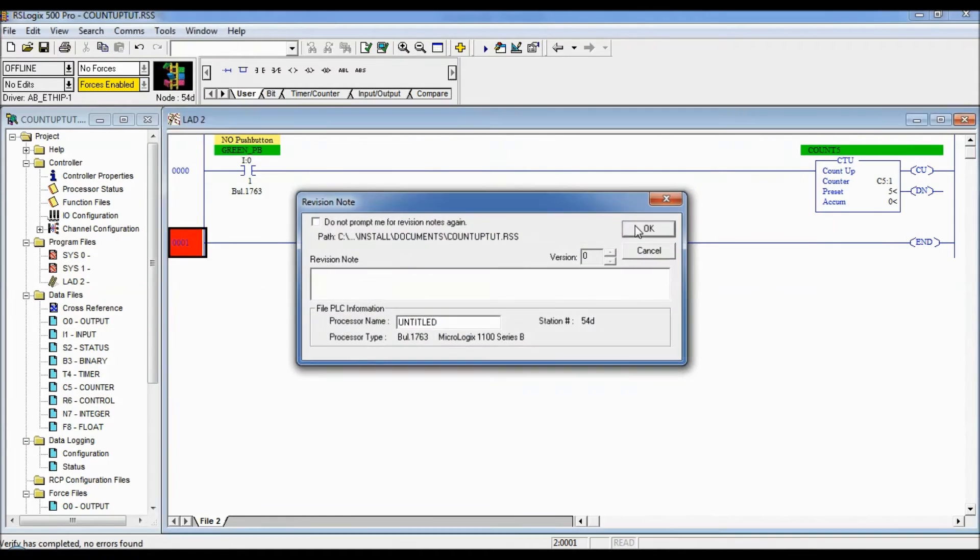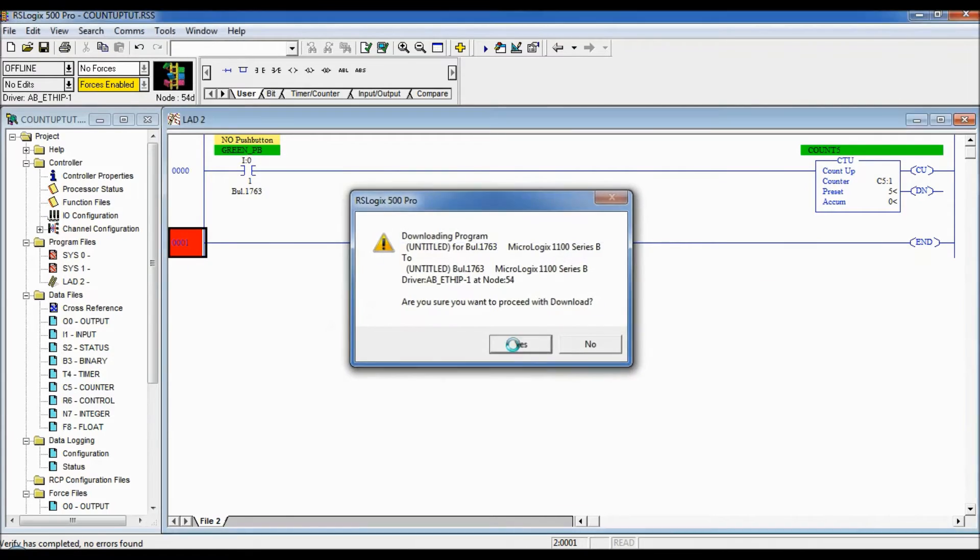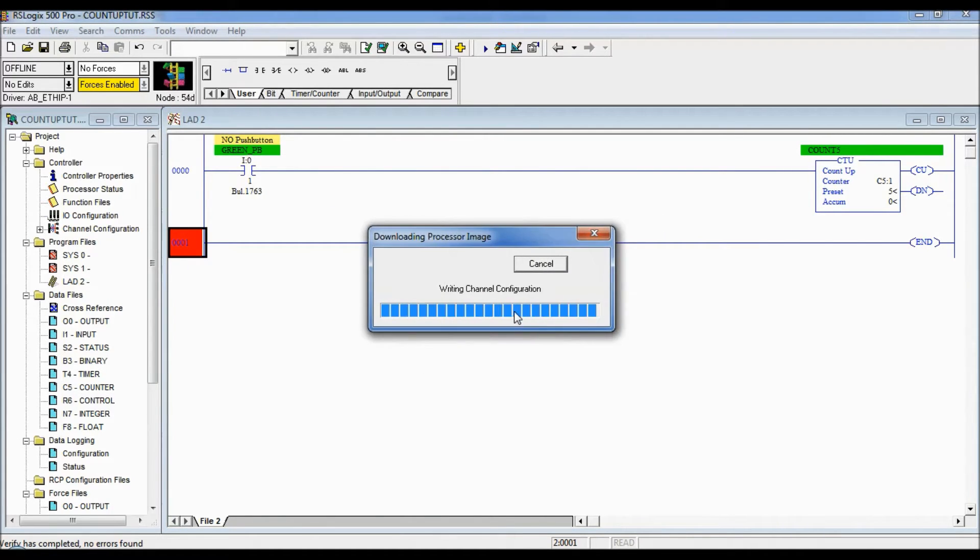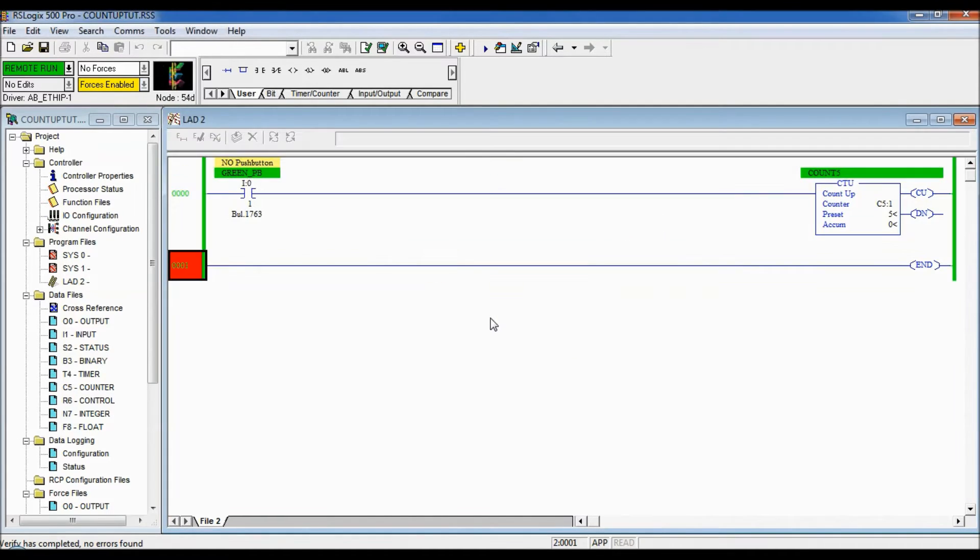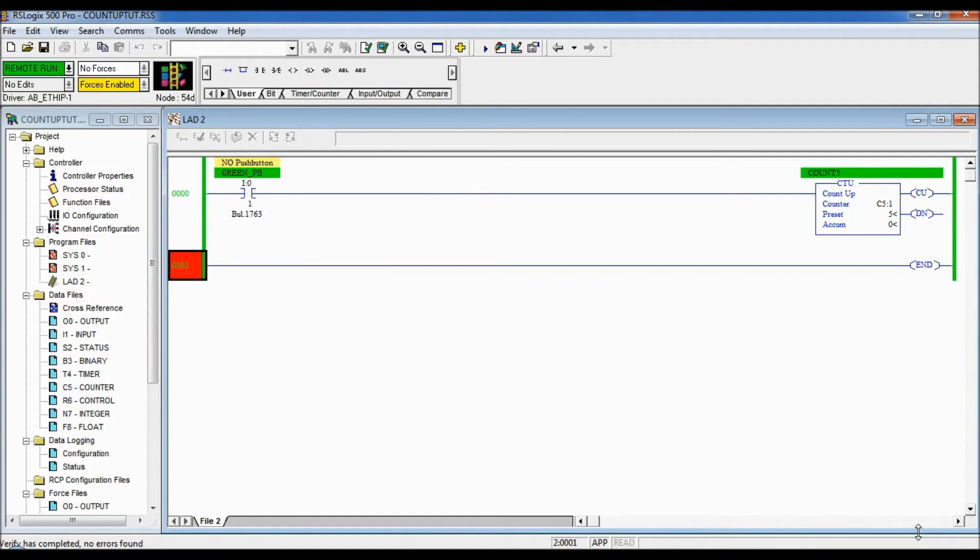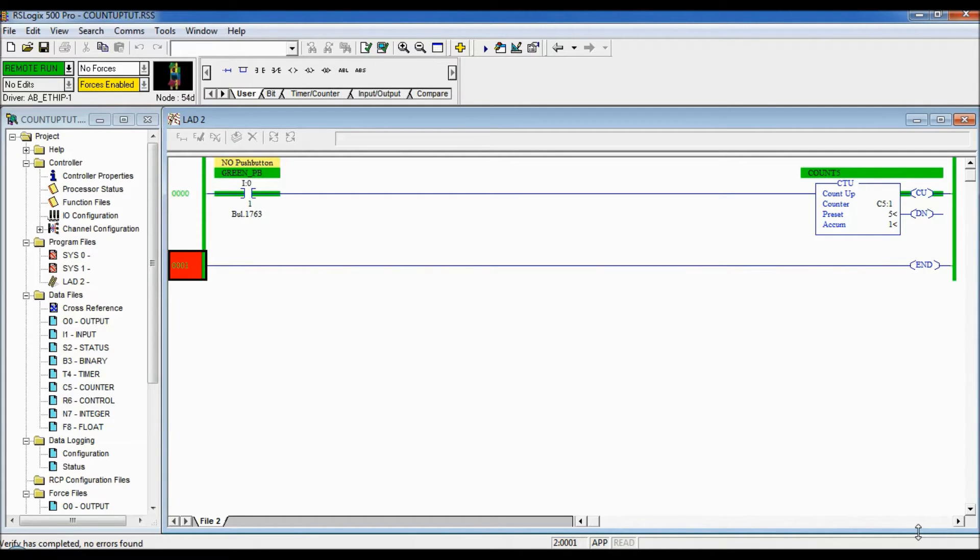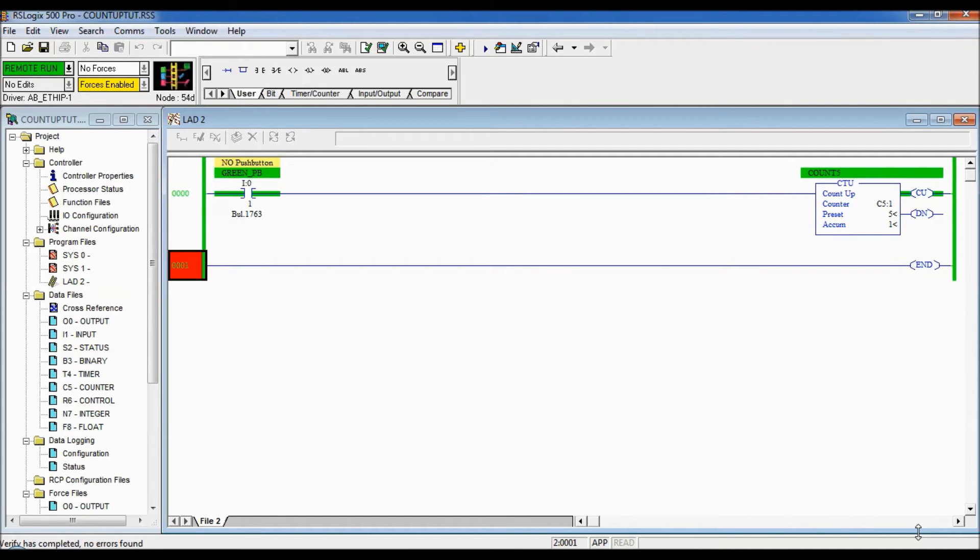Okay you can see right now the green push button is low there's no green there but when I press it it goes high and the accumulated value increments up by one and even though I keep the green push button pressed it only increments by one time. So it will not count again unless I let go of that push button so it goes false and then if I press it again it will count again.